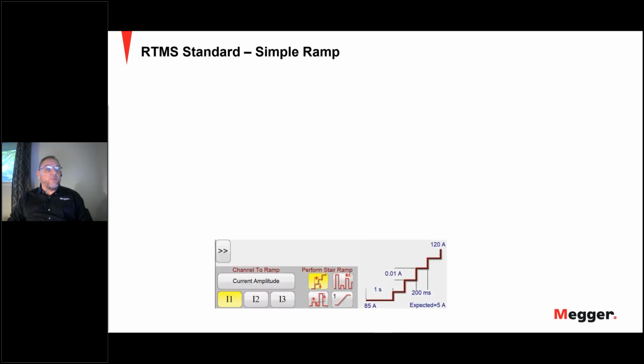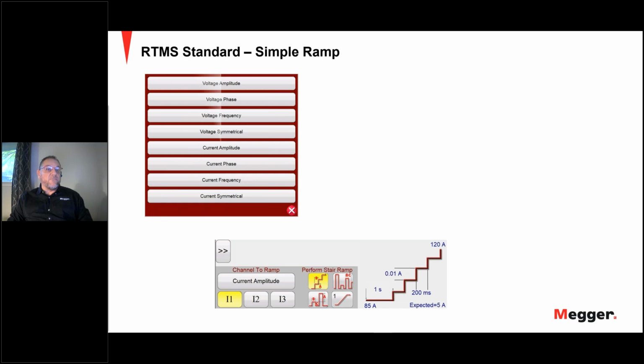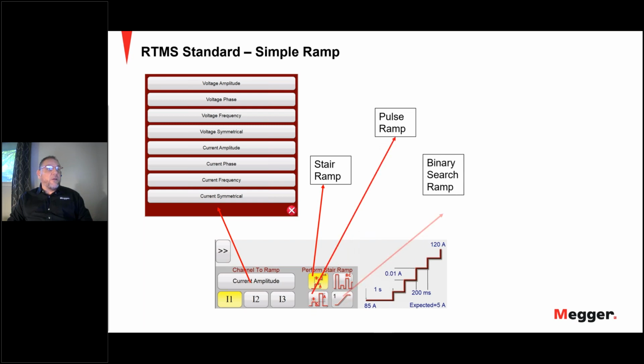All right, so moving on a little bit to the simple ramp. The simple ramp is commonly used for doing pickup or dropout tests on any type of relay. The user may select voltage or current amplitude, phase, frequency, or symmetrical components. The channel selection directly under the channel to ramp also allows the user to select which channel will be ramped. So first of all, you've got a stair ramp, pulse ramp, and a binary search ramp. And finally, you can do up to 25 ramps on the simple ramp screen.